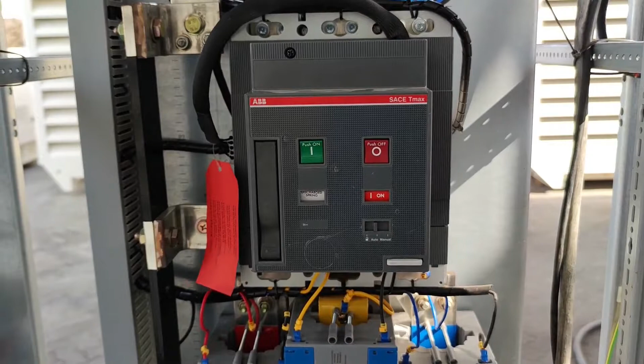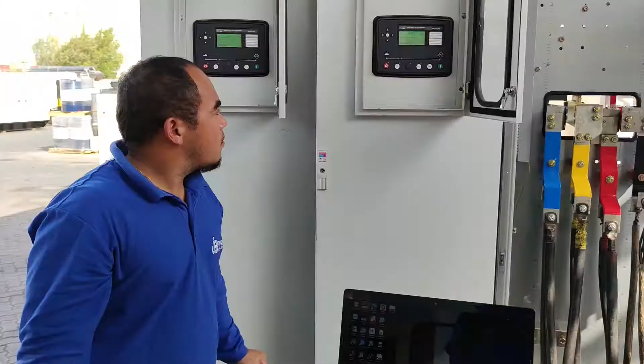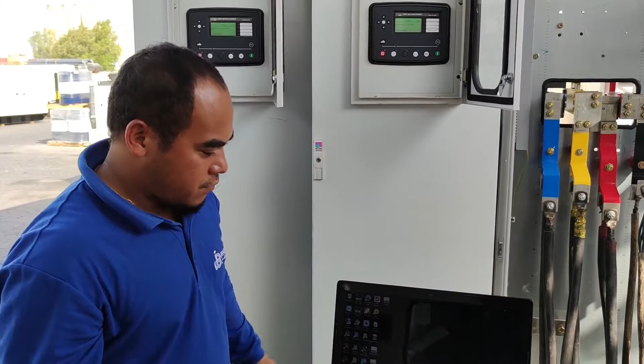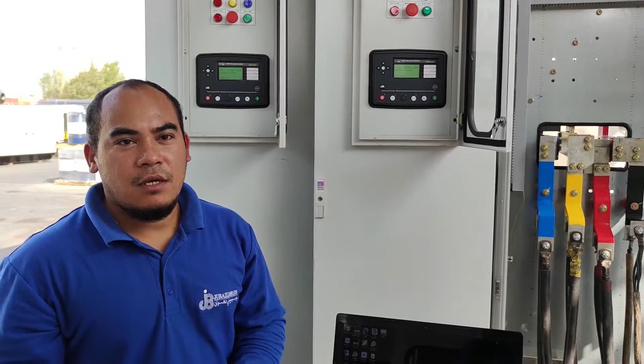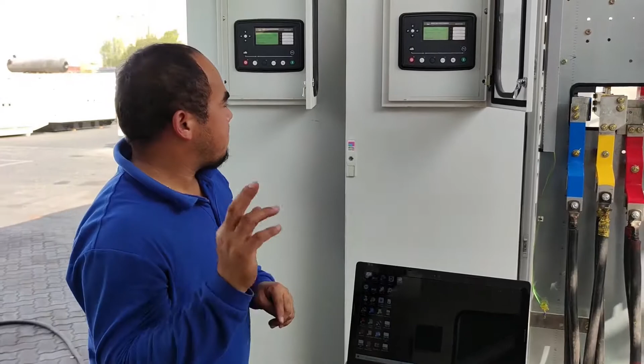Now let's start to do the synchronizing for every generator. We start first with manual sync, and after that, if there is no problem, we start automatic syncing. Okay. So now guys, we are ready to do the synchronizing for the two generators. This generator is 650 kVA. So now we will start the manual synchronizing. I'll start the generator.